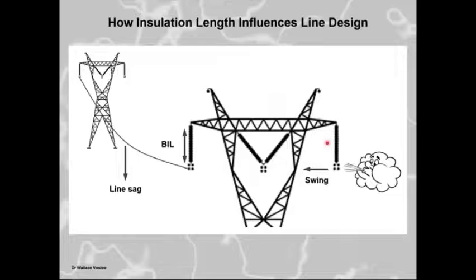Now, when you start looking at your insulation length, remember your insulation length is the distance from that metal point there to that metal point there, which determines your basic insulation level. Now, you cannot make this too long. You will then have a problem with clearance, and you need to look at your line sag. At the same time, you need to take a look at the amount of swing which you have. So you need to take into consideration clearances with swing. So you can't make this too long. Make this too long, you've got a swing problem. Make this too long, you've got a clearance problem. And that has got to do with line sag. So you can see what the influence is of your insulation length.